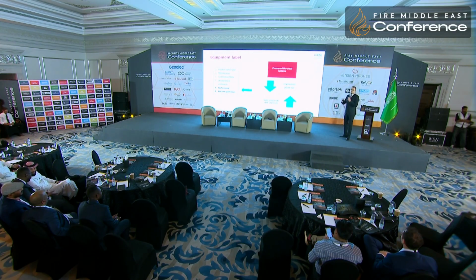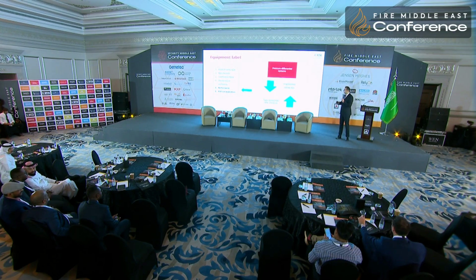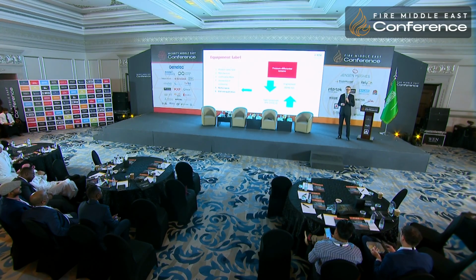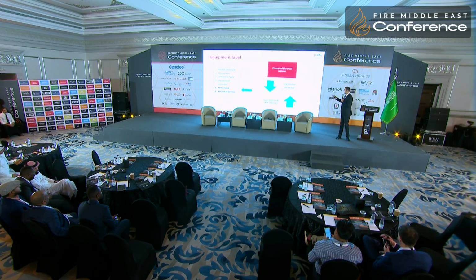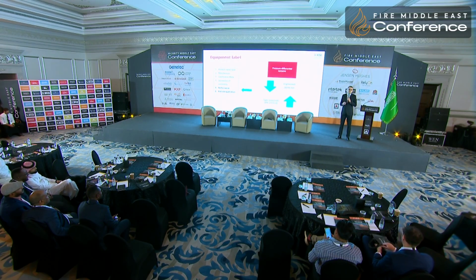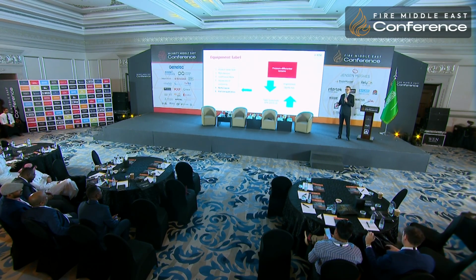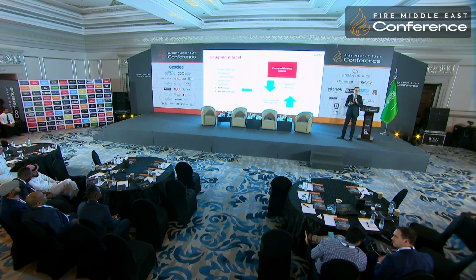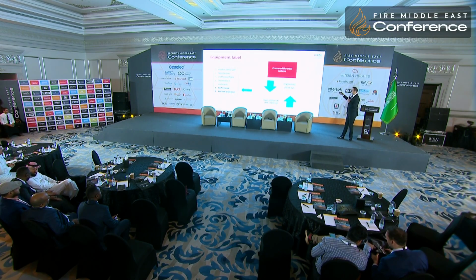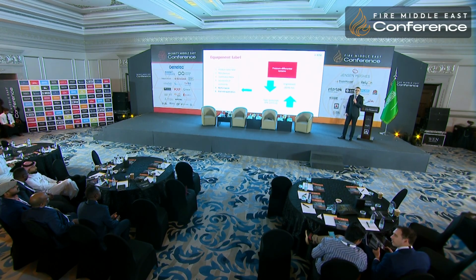And the last aspect, as you saw in the table I presented, with reference to pressure differential systems, codes and standards, NFPA 92 was not offering any technical requirements for such systems. Why? Because they are fully engineered on site. There are specific parameters required from those systems on site that need to be proved at the commissioning handover stage. So there is little testing laboratories or certification bodies can help with, but there is an alternative for type testing of kits of pressure differential systems.